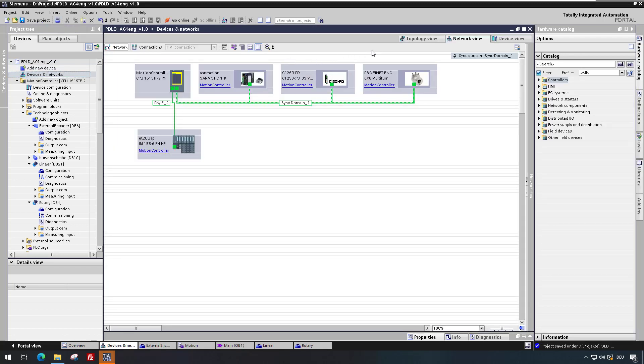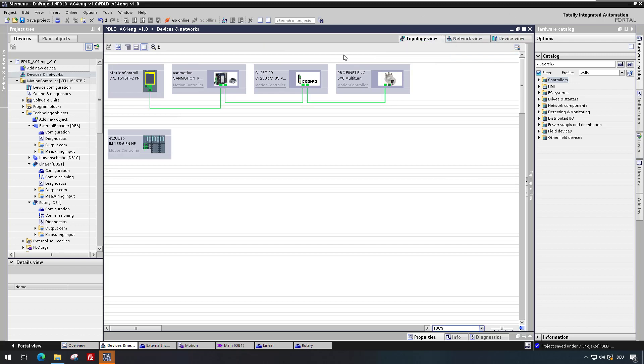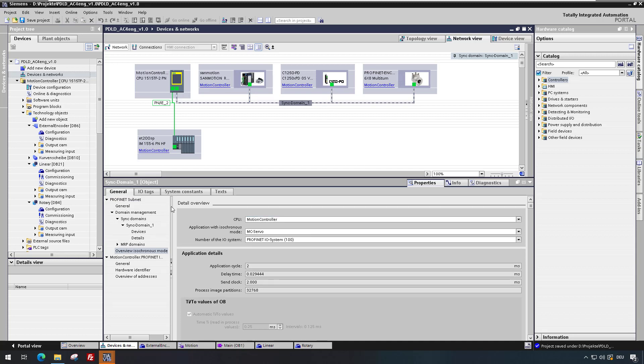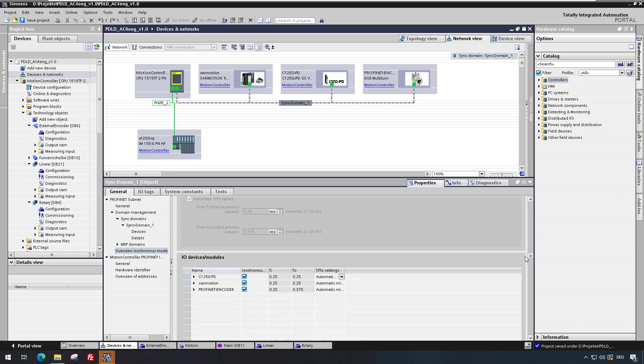The isochronous connection between all devices is secured by use of Profinet IRT. In comparison to unsynchronized communication, like for example in application class 1, a topology of the interconnections between the controller and devices must be configured. The details of the sync domain enable adjustment of the TI and TO times if needed for every single participant.